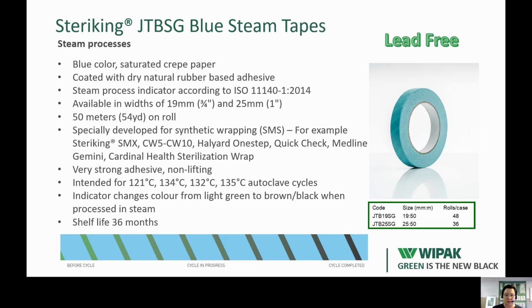And then the blue steam tape that is intended also for steam process because it's printed with a process indicator for steam. This is still having this dry natural rubber-based adhesive, so it contains small amounts of latex. And this is made from blue crepe paper. And then it's available in two different widths, 19 millimeters and 25 millimeters, and 50 meters on a roll. And these blue tapes, the neutral blue tape and also this steam tape with steam indicator, are specially developed for closing the bags made from synthetic wrapping materials. So, for example, our SMX and then Halyard and Medline and Cardinal wraps.